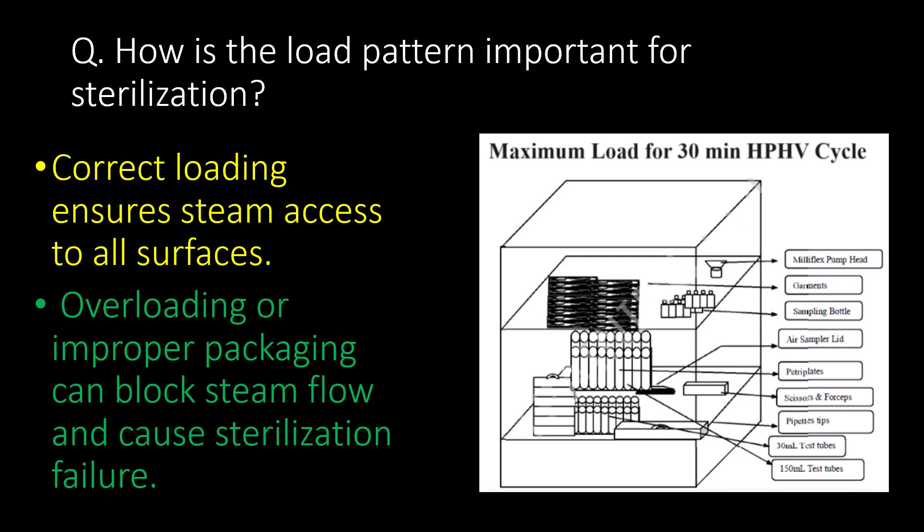How is the load pattern important in sterilization? Correct loading ensures steam access to all surfaces. Overloading or improper packaging can block steam flow and cause sterilization failure.